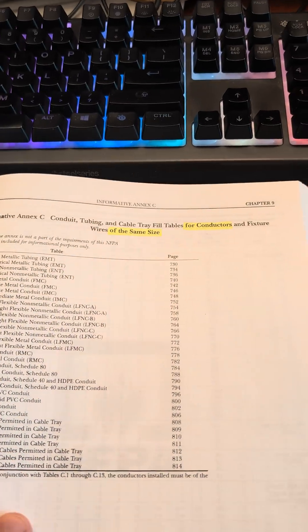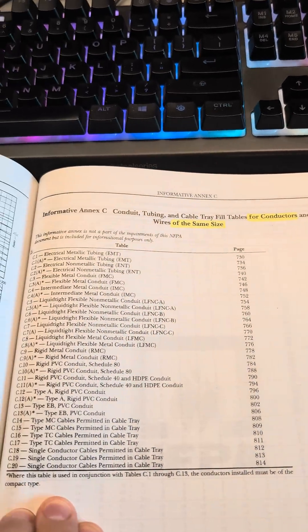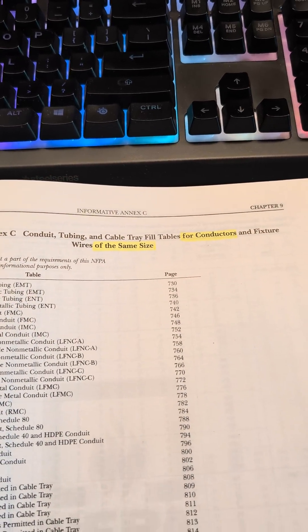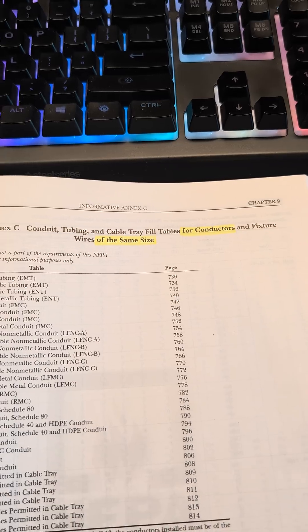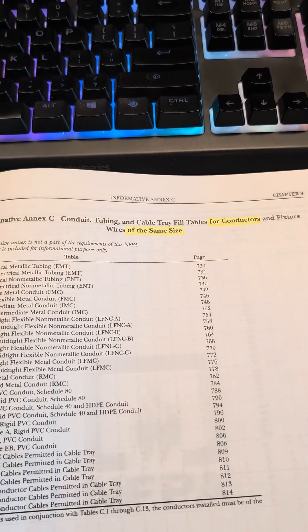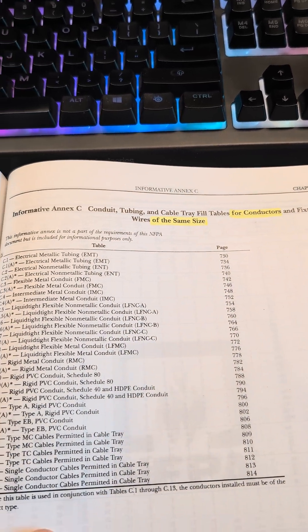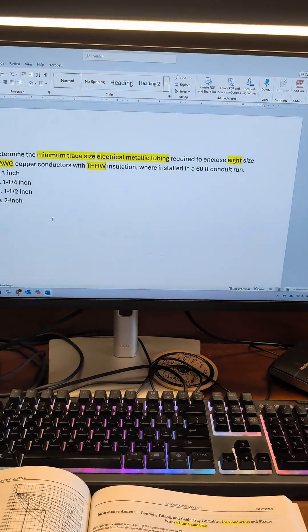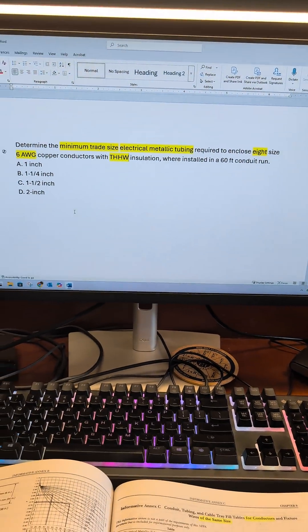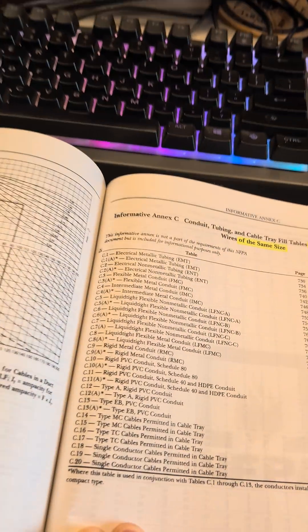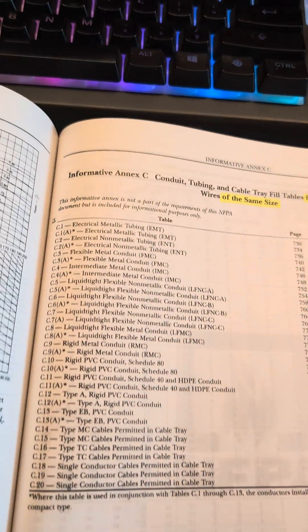Now, the big important part with this table is, I have it highlighted up there, for conductors and fixture wires of the same size. They're all of the same size. They're not dissimilar sizes, so we can use this Annex.